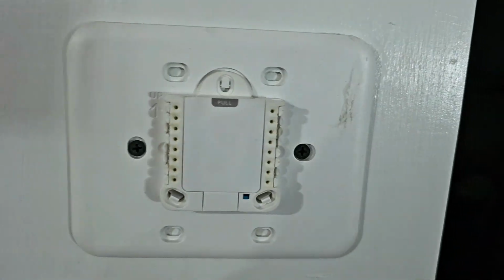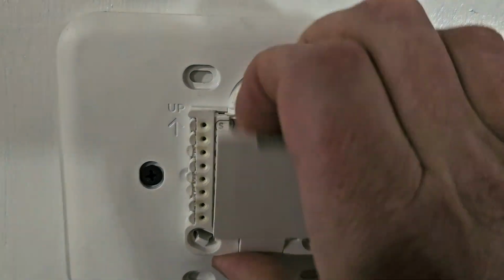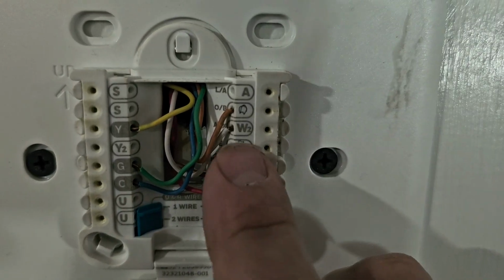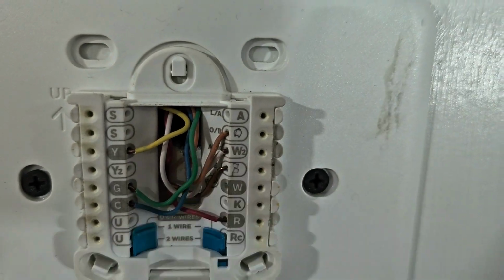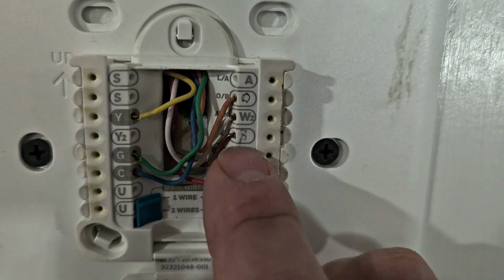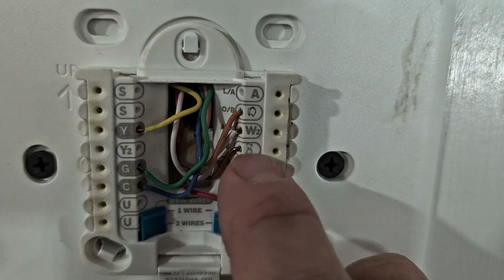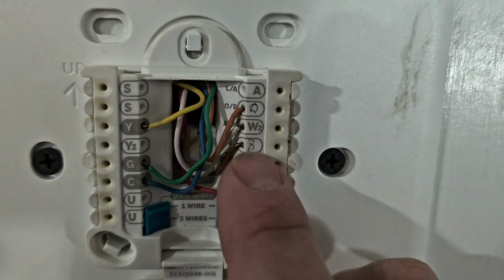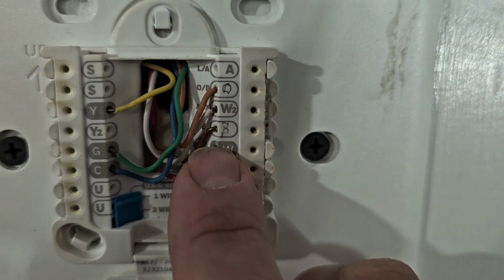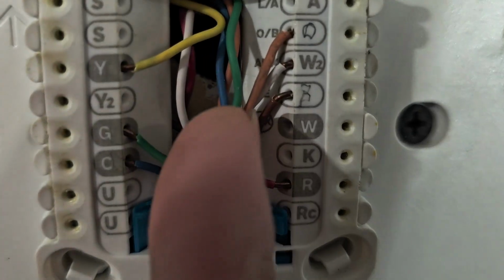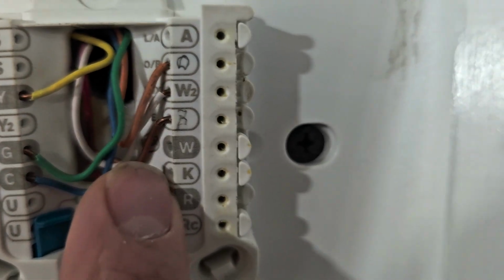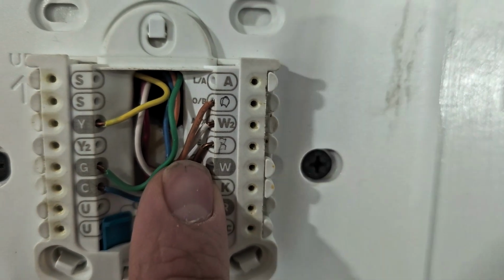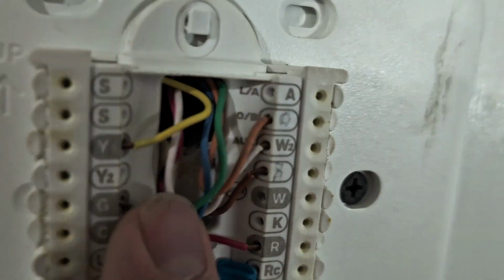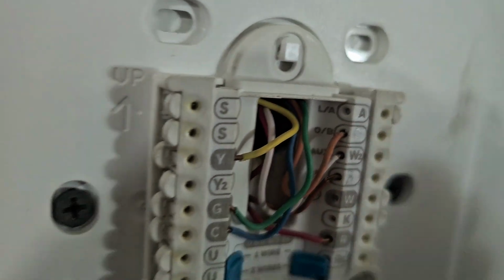Now we need to make sure it's actually hooked up. So we're gonna take the thermostat off the wall, and then we're gonna look at the terminals that say W2, which is auxiliary heat, and then this one is labeled E. Can't really see it, it's hard to see it, but that's E. So that means it is hooked up. It's a brown, oh, now you can see it right there. So it's a brown wire that controls the emergency heat. A white wire that controls the auxiliary heat, aux, A-U-X.